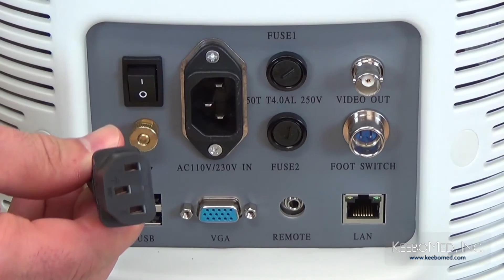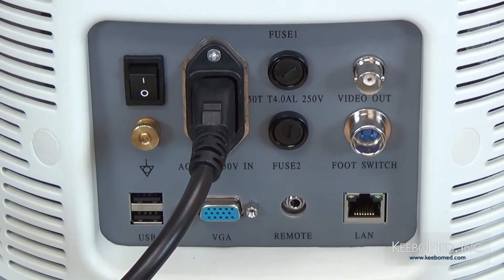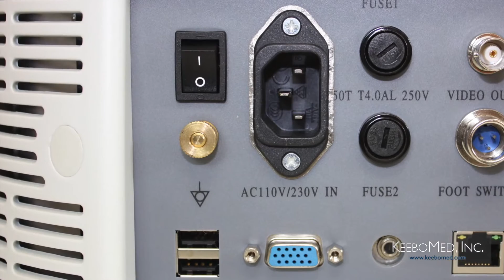Step number 1. Connect the plug of the power cord to the AC power in socket at the rear panel of the system. Step number 2. Connect the other end of the power cord into the AC power supply socket. The 8300 also has an equal potential terminal that is used to equalize the grounding terminals between the system and other electronic equipment that may be connected to the system.